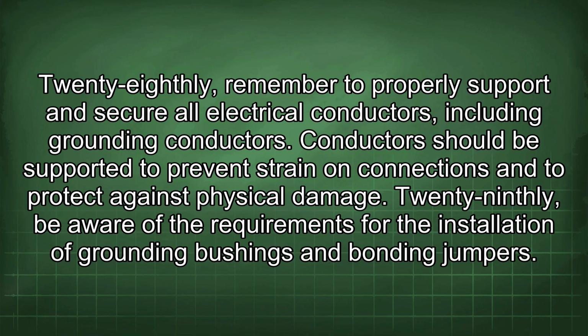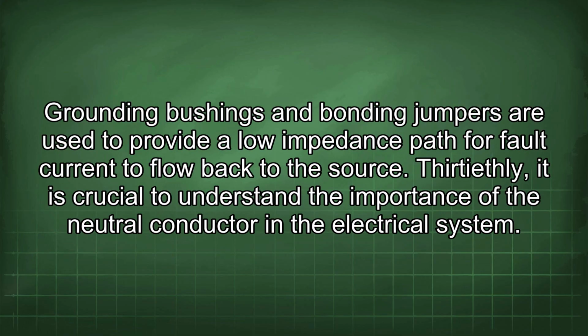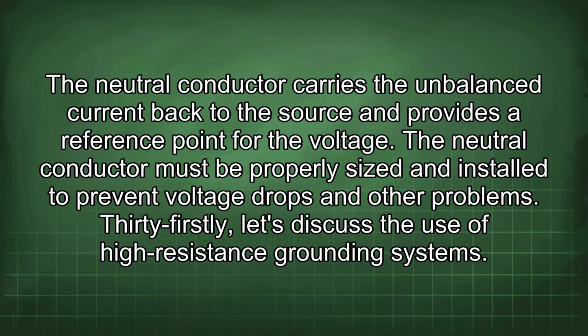28thly, remember to properly support and secure all electrical conductors, including grounding conductors. Conductors should be supported to prevent strain on connections and to protect against physical damage. 29thly, be aware of the requirements for the installation of grounding bushings and bonding jumpers. Grounding bushings and bonding jumpers are used to provide a low impedance path for fault current to flow back to the source. 30thly, it is crucial to understand the importance of the neutral conductor in the electrical system. The neutral conductor carries the unbalanced current back to the source and provides a reference point for the voltage. The neutral conductor must be properly sized and installed to prevent voltage drops and other problems.